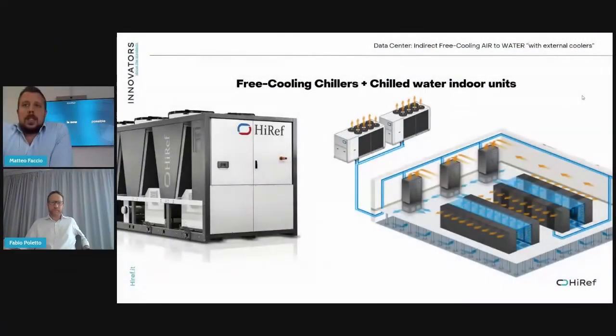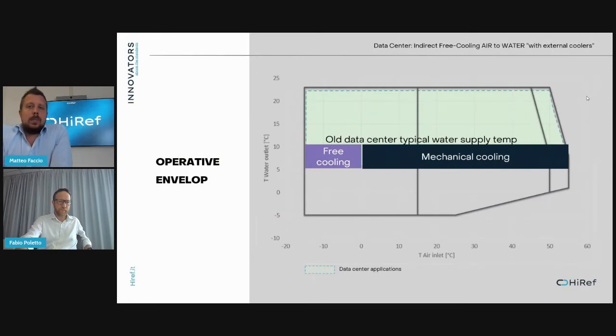Okay, but with such a high temperature in the cold water production, so you mentioned 20-30, how is it possible in this kind of application to use mechanical cooling? You mentioned the use of a chiller, for example. So how is it possible? Yeah, this is one key point, and of course we need to take some technology advantage, and it means that we can use a new type of compressor and a new type of refrigerant that gives the possibility to operate with an enlarged envelope range.